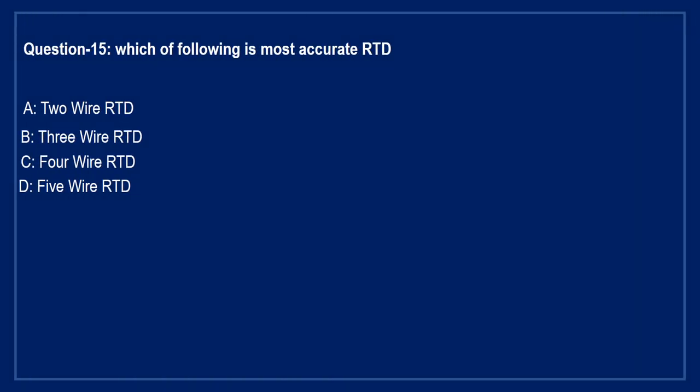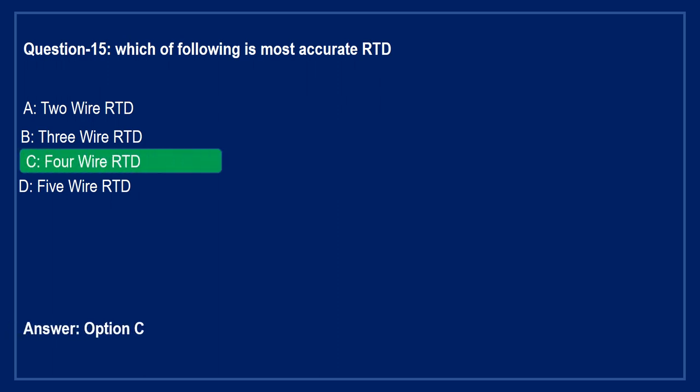Next question: which of the following is the most accurate RTD? Option A: 2-wire RTD. Option B: 3-wire RTD. Option C: 4-wire RTD. Option D: 5-wire RTD. The correct answer is Option C, 4-wire RTD. Yes friends, 4-wire RTD is the most accurate because in 4-wire RTD, the lead resistance is minimized.